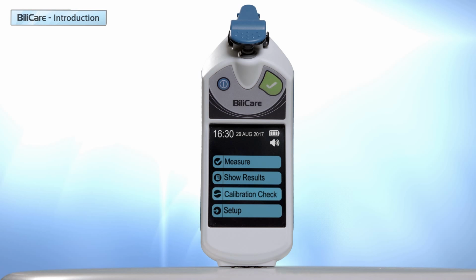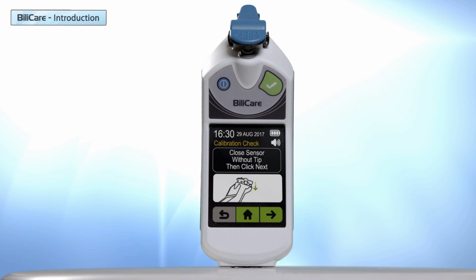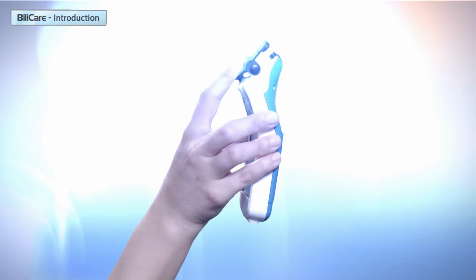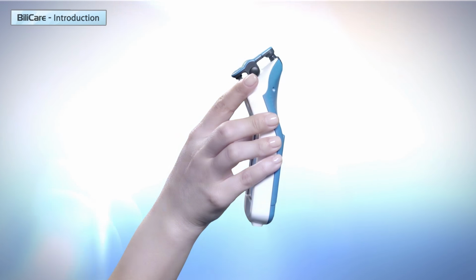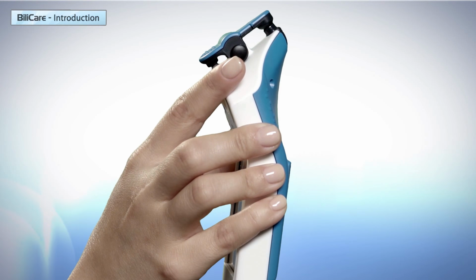Let's press calibration check. This procedure verifies that BiliCare is working properly. Follow the instructions on the screen. The first screen asks the user to close the clip, meaning that no tip or cover should be on the sensor.